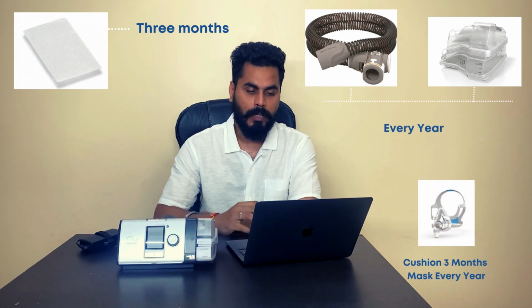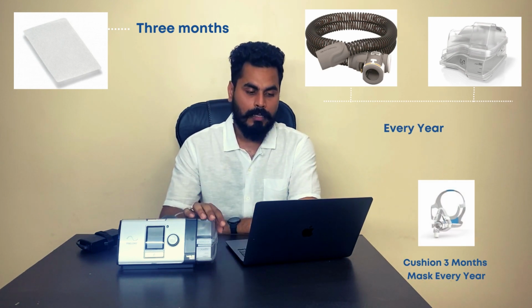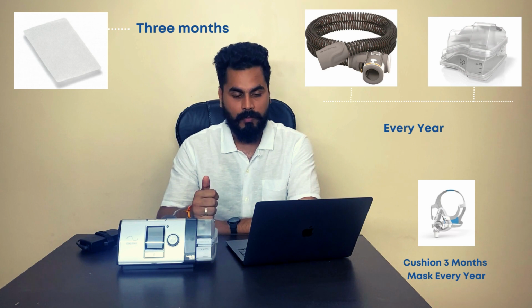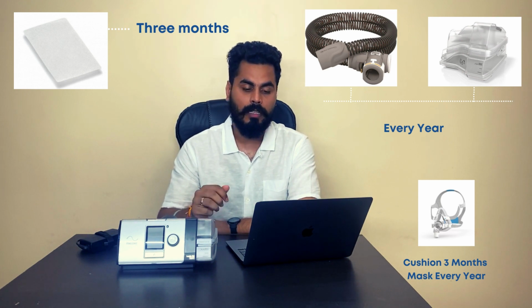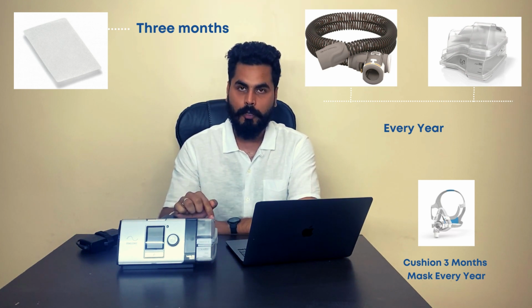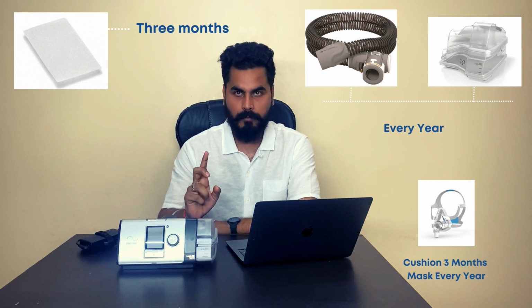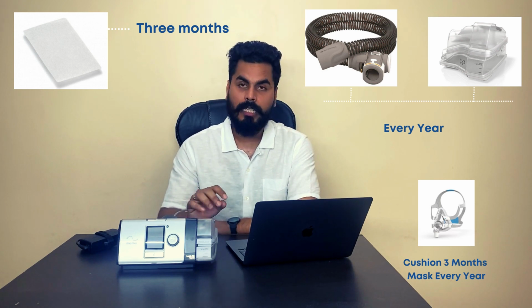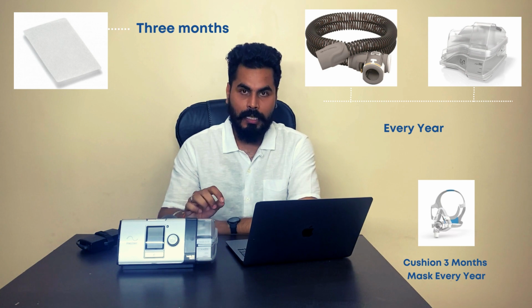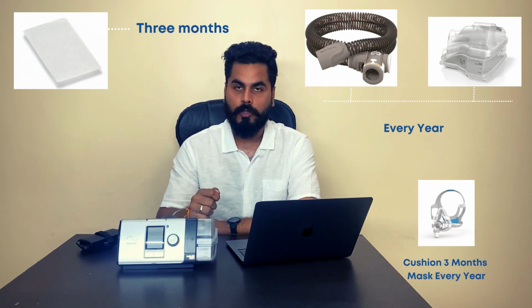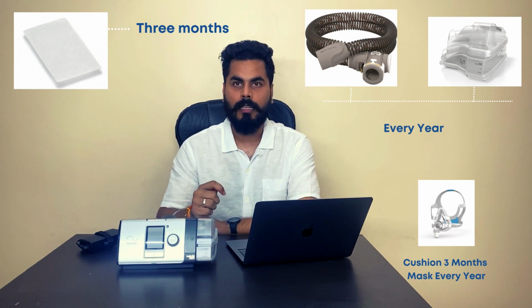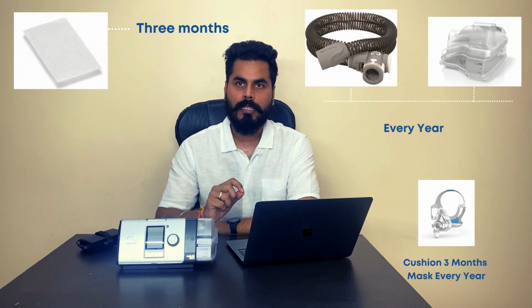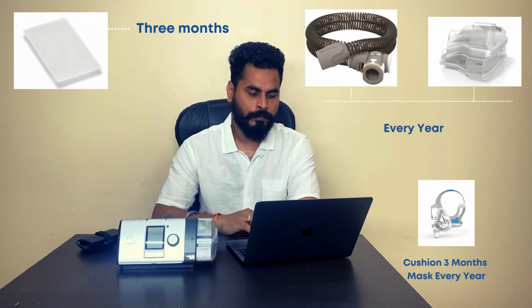Now how do you have to maintain this device? In this device, you have to clean the filter every 15 days and you have to change the filter every 3 months. Change the humidifier and the tubing every year. Clean the humidifier every 15 days. You have to change your mask cushion and change the mask in 3 months and 12 months respectively.